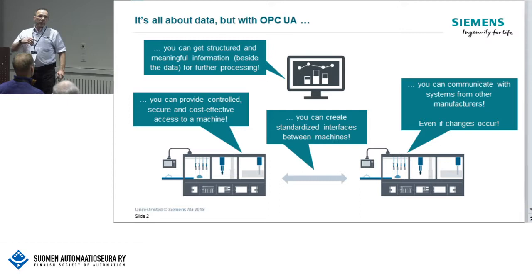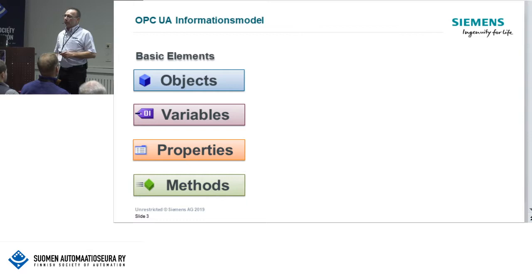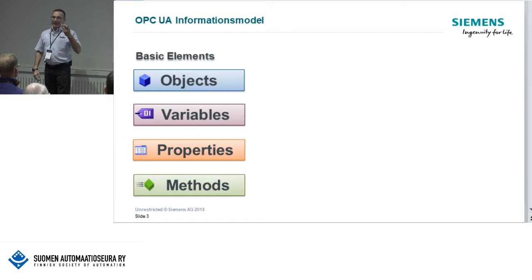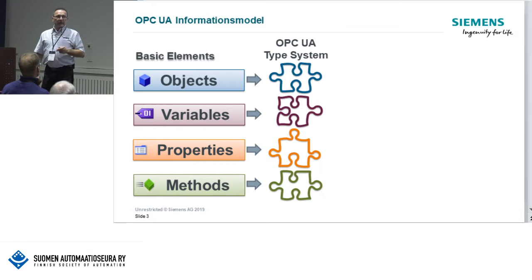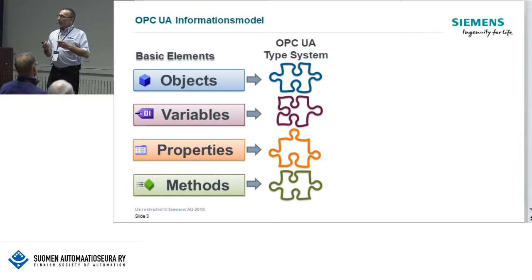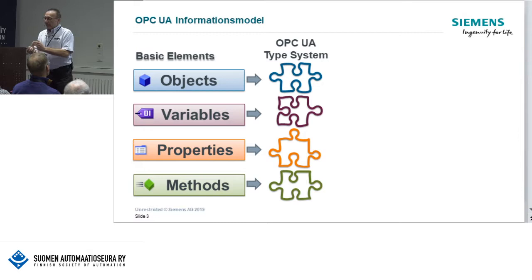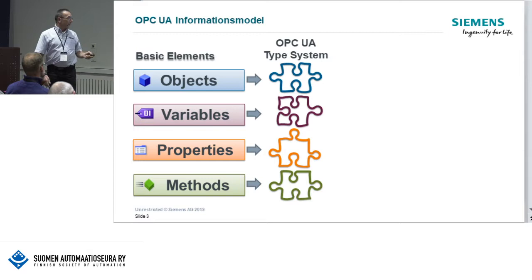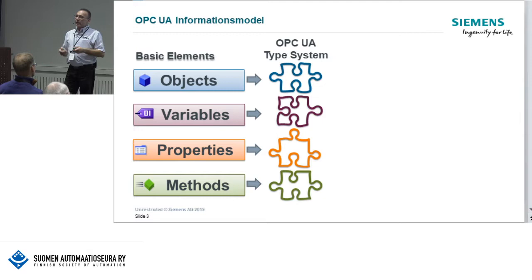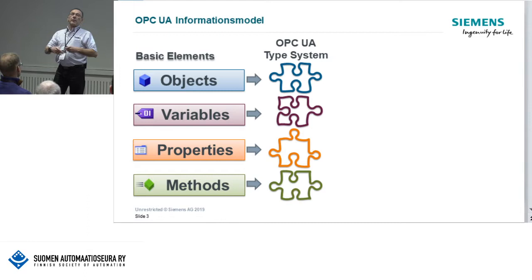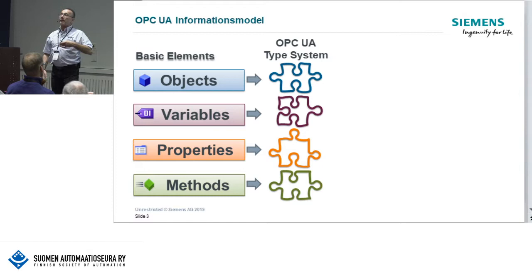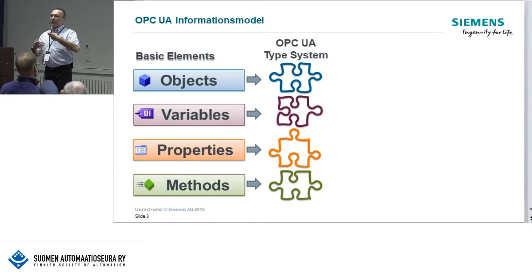I will give you an example of how you can do it with a Siemens S7-1500 PLC, covering the basic elements of OPC UA. There are existing object types, variable types, properties, methods, and so on — it's always clearly defined as an OPC UA type system. A companion specification defines, for example, a machine type for rubber machines, with variables, properties, and methods. Methods are very important in OPC UA because they reduce complicated handshakes between devices — the old PLC handshake sequence of request, acknowledge, send, and confirm is replaced by a straightforward method call.